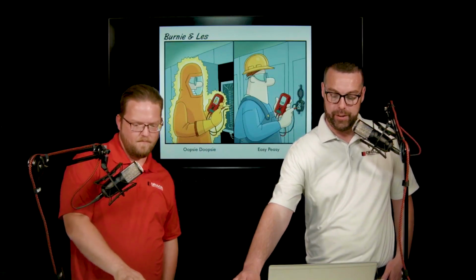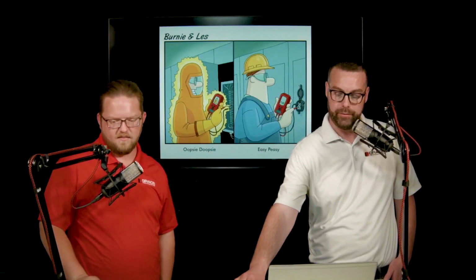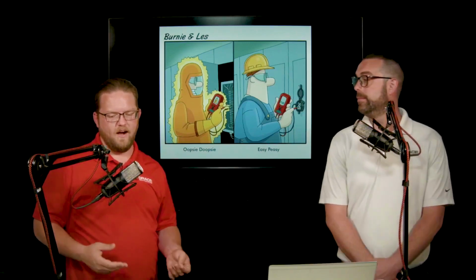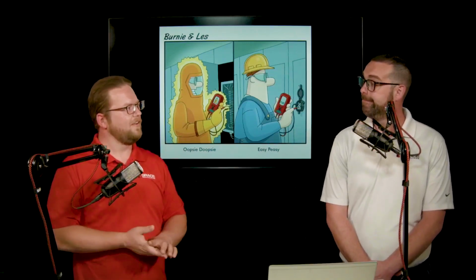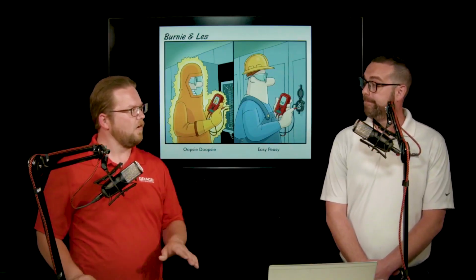So I think there might be a couple more quick questions. We had some on motors and VFDs. Do motors running on VFDs, versus contactors or starters, contribute to available fault current? VFDs don't contribute to the available fault current. They may create some noise and have some impact, but they won't contribute to the potential fault current of the system. Quick answer to get that one out of the way.